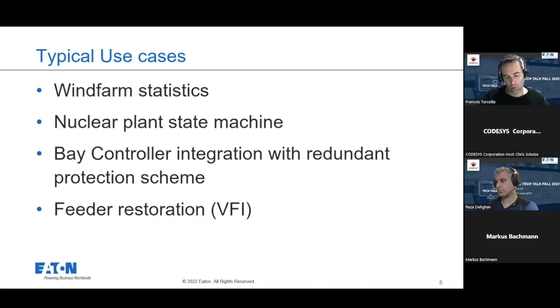A bay controller is where we concentrate information coming from different devices, and CODESYS can decide if it's going to operate through one protection or the other. So that's what we did in this project: concentrate information, send the control to protection A or protection B, and decide which one should do it. If it fails on one protection, we can send it to the other. So the CODESYS engine was able to take those decisions and send the correct information. And based on the result of one command, it can send it back to the other protection and make sure that the command is sent correctly.